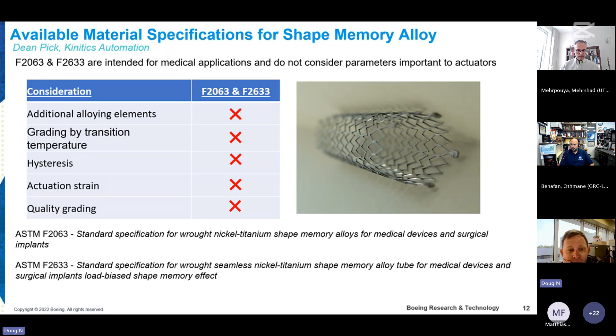I'll note here at the bottom, I know I'm using the ASTM designations quite often. That may be a bad habit within the standards community. But I will note F2063 is the material specification for wrought nickel titanium for medical devices and surgical implants. So, great. Just a few more slides on where we're going with this material specification. The first slide looks at material specification grading, where we could grade by alloying component, then the subgrade would be the transformation temperature, and then the subgrade would be material quality. This allows us to set different grades for transformation temperatures and material quality.